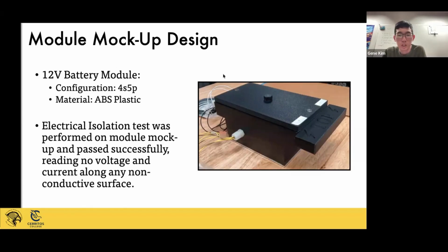We also performed an electrical isolation test on the enclosure, and it passed with no voltage or current detected on any of the non-conductive ABS surfaces. This confirms that the CNC-machined ABS housing provides the electrical insulation and safety performance required for our system.